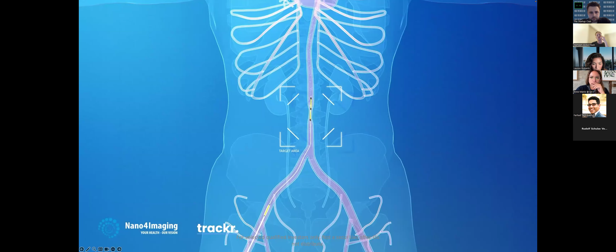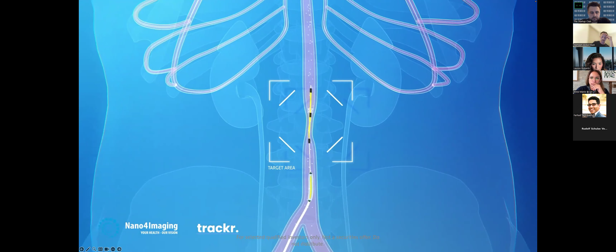Now that the wire is positioned in the target area, the angioplasty balloon catheter can be moved over the wire to the region of interest. It has 2 markers on each side and can be moved over the guide wire towards its distal position. The 2 balloon markers can be matched to the 3 markers of the guide wire pre-positioned in the stenotic area. The guide wire is then retrieved to allow balloon inflation. At all times, the markers on the tapered tips of the balloon remain visible. So if you see the inflating balloon, you can imagine that you also can do stenting and many other procedures.